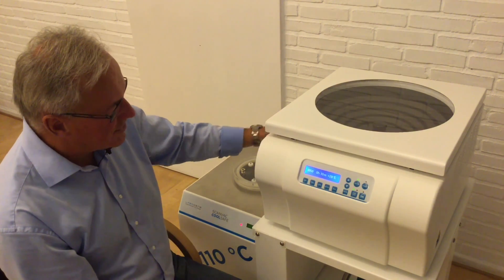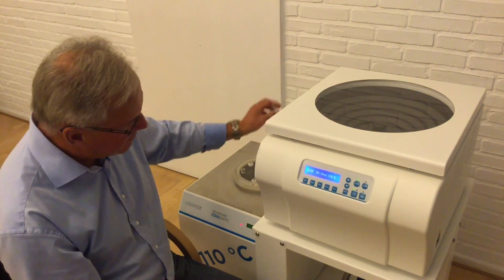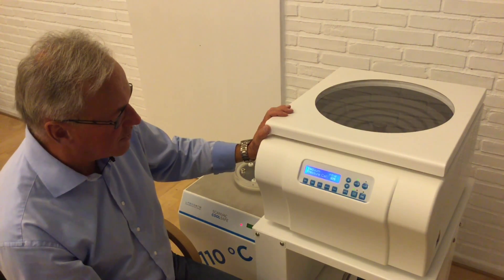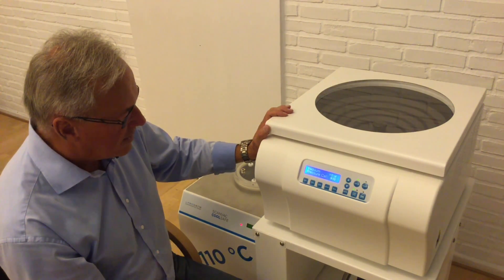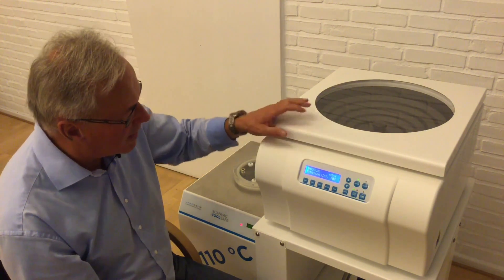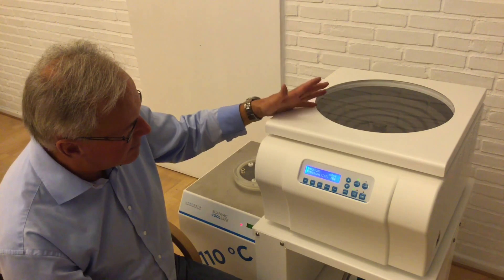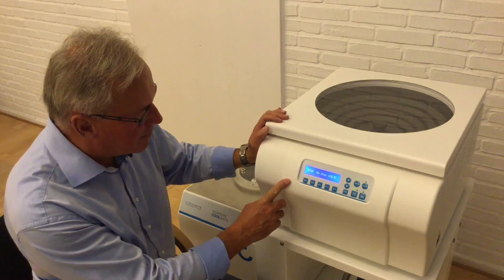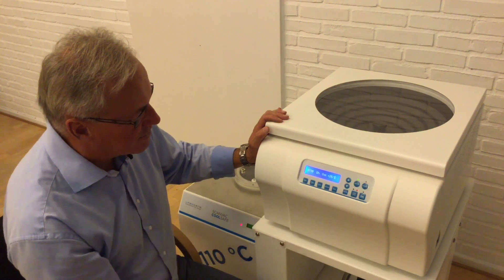Now the pump starts and we begin to have vacuum — low pressure. You can see by pressing the button that the pressure is now going down. It will reach approximately one hectopascal or one millibar. It will operate for the set time of ten minutes as keyed in as a set point. But you can, if you like, just switch it off.